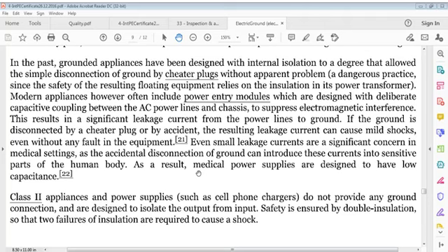Modern appliances, however, often include power entry modules which are designed with deliberate capacitive coupling between AC power lines and chassis to suppress electromagnetic interference. This results in a significant leakage current from power lines to ground.